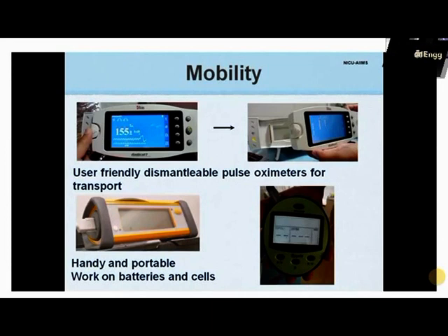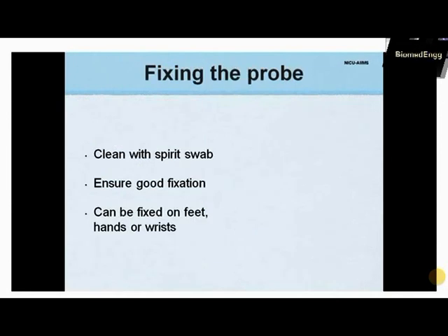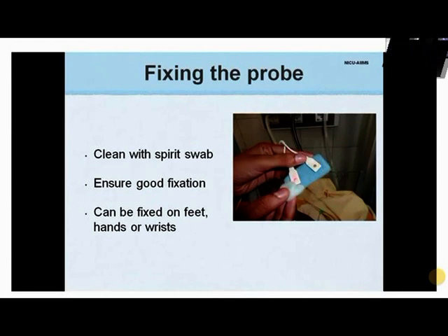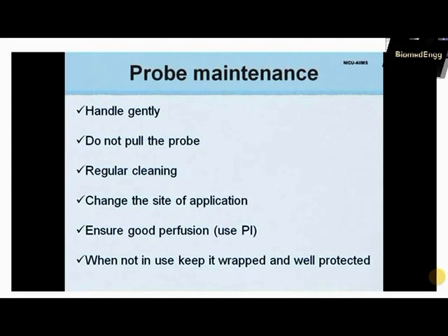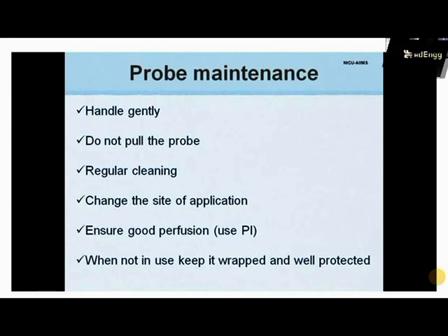Some pulse oximeters have rubber frames for sturdiness during transport. Whenever a probe is applied for the first time, it must be cleaned with a spirit swab, then secured so that one end is on the dorsum and the other on the ventral aspect of the monitoring site. Ensure secure fixation of the flex wrap. Handle the probe gently, never pull it from the site, and change the application site regularly, ensuring good perfusion with the aid of perfusion index if available.